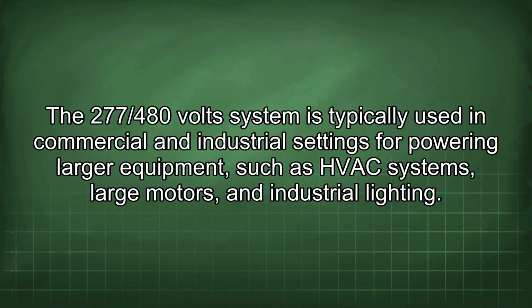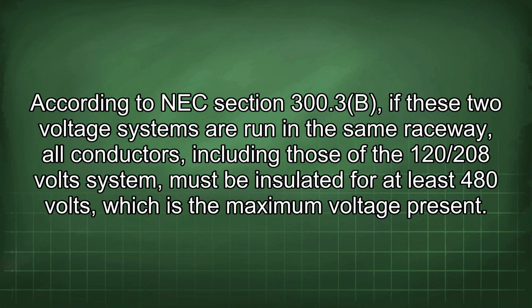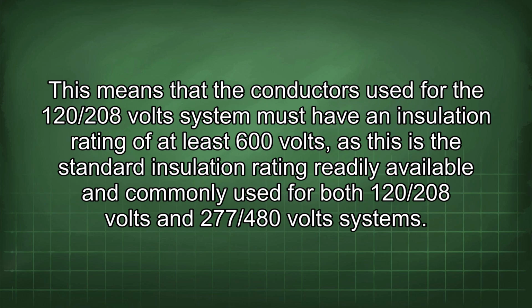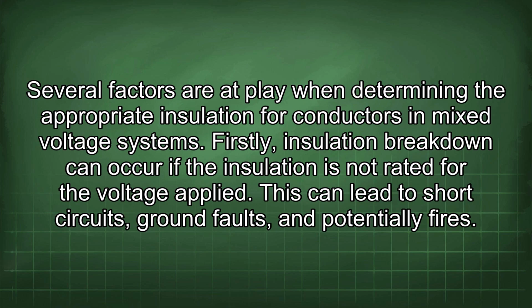According to NEC Section 300.3(B), if these two voltage systems are run in the same raceway, all conductors, including those of the 120/208 volt system, must be insulated for at least 480 volts, which is the maximum voltage present. This means that the conductors used for the 120/208 volt system must have an insulation rating of at least 600 volts, as this is the standard insulation rating readily available and commonly used for both 120/208 volts and 277/480 volts systems.